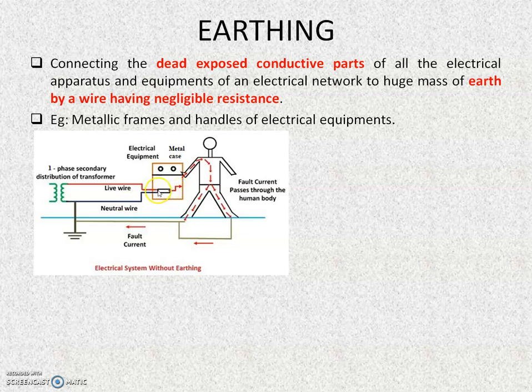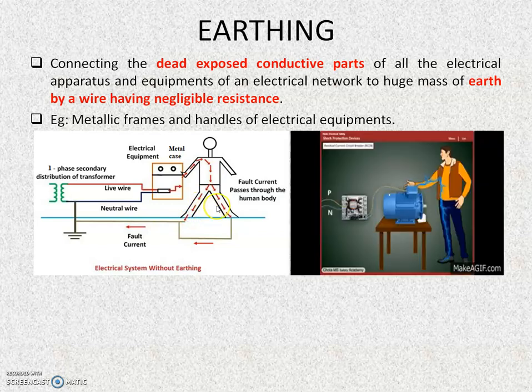Now what happens if there is a leakage or the insulation of the live wire has some issues and the current reaches the metal case? Unknowingly, if a person touches the metal case, the current will take a path like this to the ground and the person will experience an electric shock, as seen from the diagram. In this case, we have only phase and neutral connection and maybe due to some fault, potential may appear on the metallic case, and if a person is touching the metallic case, he will experience a shock. So this is the case where there is no earthing.